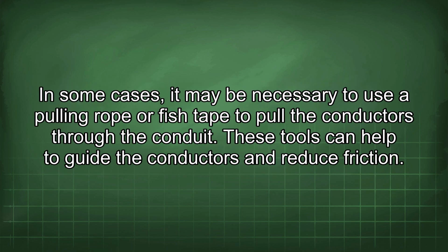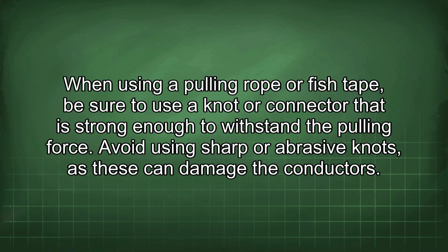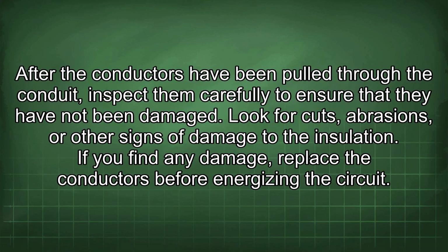In some cases, it may be necessary to use a pulling rope or fish tape to pull the conductors through the conduit. These tools can help to guide the conductors and reduce friction. When using a pulling rope or fish tape, be sure to use a knot or connector that is strong enough to withstand the pulling force. Avoid using sharp or abrasive knots, as these can damage the conductors. After the conductors have been pulled through the conduit, inspect them carefully to ensure that they have not been damaged.